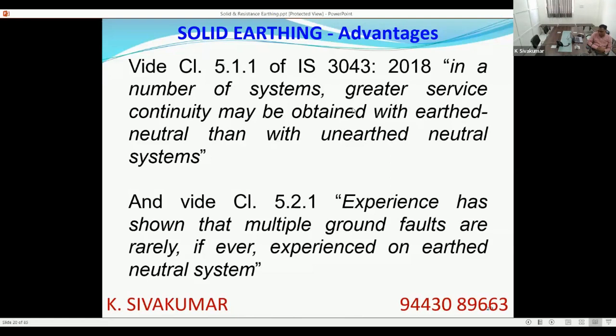But subsequently, we have also seen that sooner or later, the single line to ground fault will culminate into a double line to ground fault. The second line insulation will be stressed, and sooner or later the second line also will short circuit with earth. So the LG fault will become an LLG fault. The magnitude of an LLG fault is very high, so definitely your fuse or breaker will blow or trip and isolate the faulty zone. So the advantage of service continuity is definitely lost.